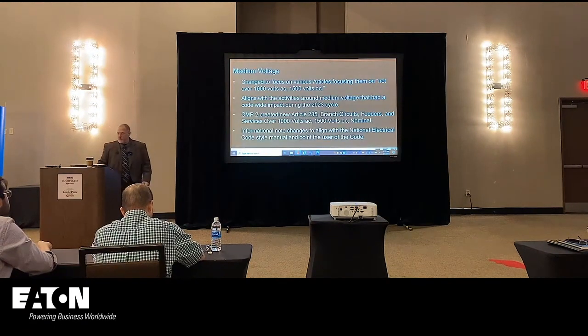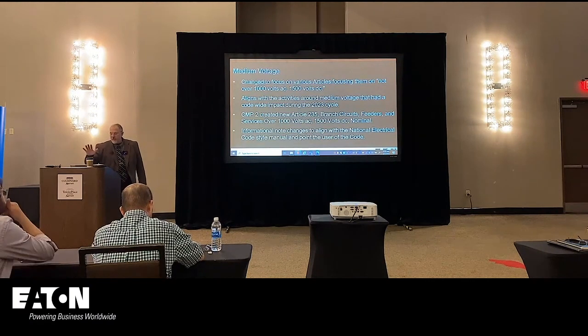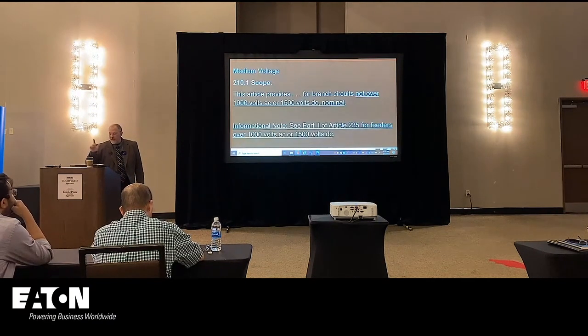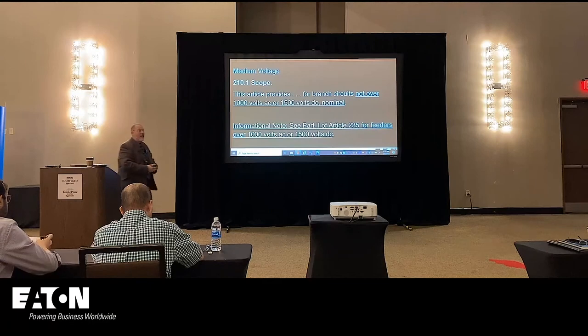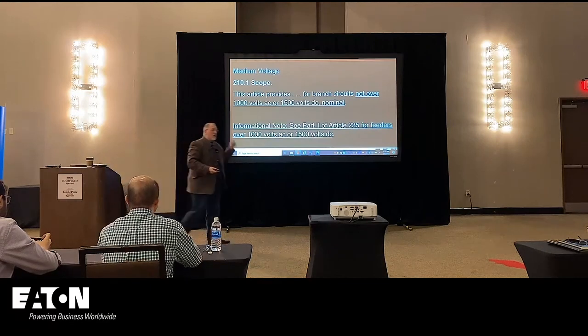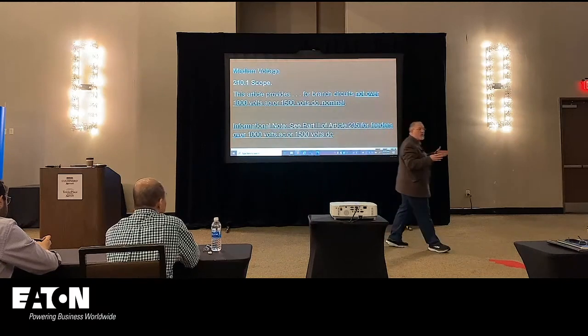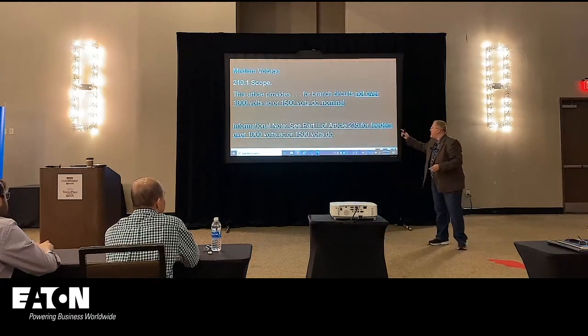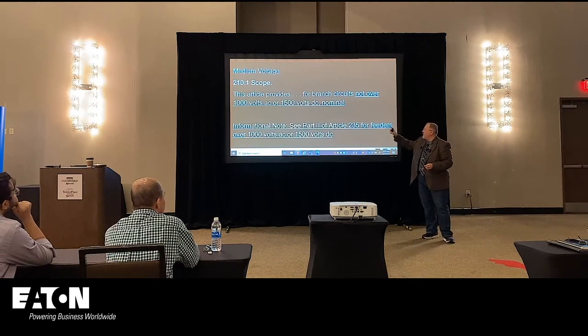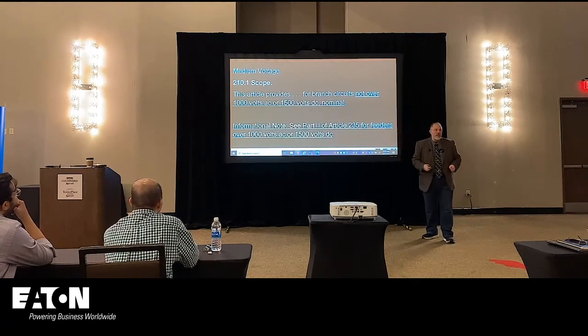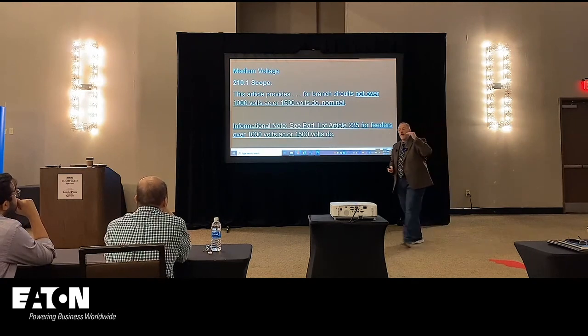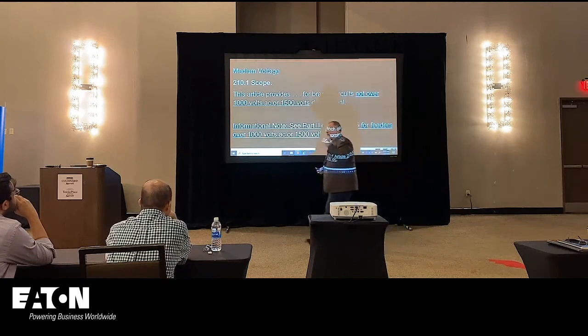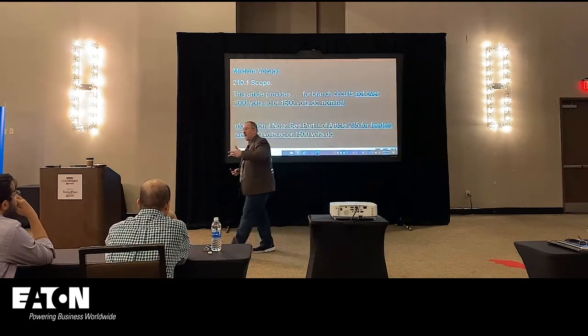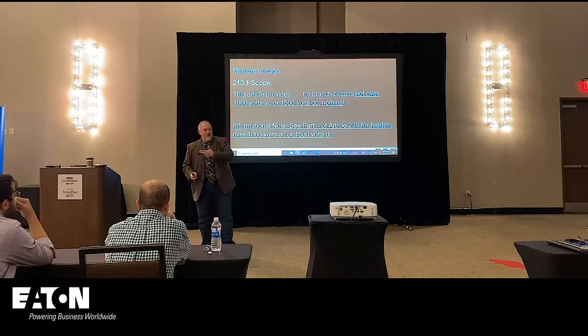I'm not going to go over it again. We already talked about medium voltage, 235, et cetera. So all of that. This is what you'll see now. So now Article 210, since we stripped out medium voltage, we had to change the scope of each of the articles. So now Article 210 just says not over 1,000 volts AC or 1,500 volts DC nominal. If you want the requirements for over 1,000 volts AC and 1,500 volts DC, then you go to where?